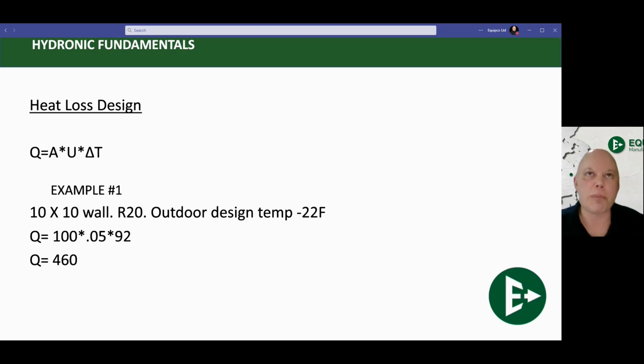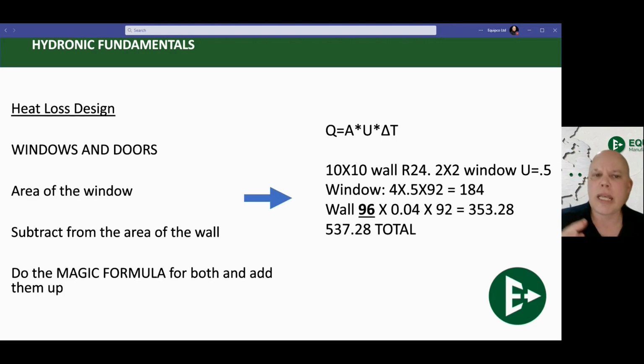You would need 1500 BTUs. Sorry, that room would lose 1500 BTUs per hour that you need to replace with heat from an air handler, radiators, or radiant or something like that. Then you get into windows and doors. Windows and doors use the same formula. You just need to kind of extrapolate them from the wall.